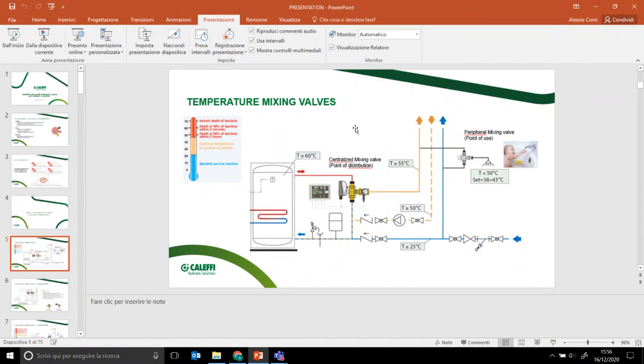So this is the one, right? Which mixing valve are they referring to? The centralized one performing the thermal disinfection, or the secondary one at the point of use? Yeah, I think it's the secondary one. To be honest, it's to do with the pasteurization loop. Normally, it is not failing since it can withstand very stressful pressure conditions. It is engineered to comply with a 6:1 pressure ratio. But in case of failure during the thermal disinfection, there is of course a potential risk for the user. That's why we recommend proper water treatment. If the water is treated properly, the inner materials of these devices are anti-scale, so their performance is very, very good. The resistance to scale and dirt is very, very good. And furthermore, in the Caleffi catalog, there is also a further thermostatic anti-scald element in order to give even more protection to the users.